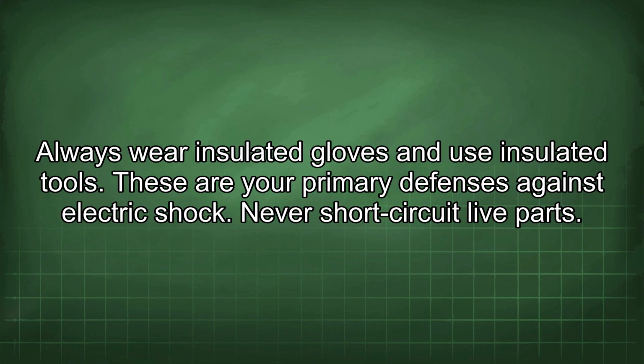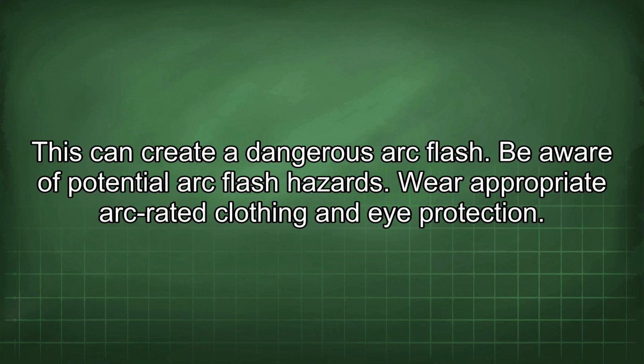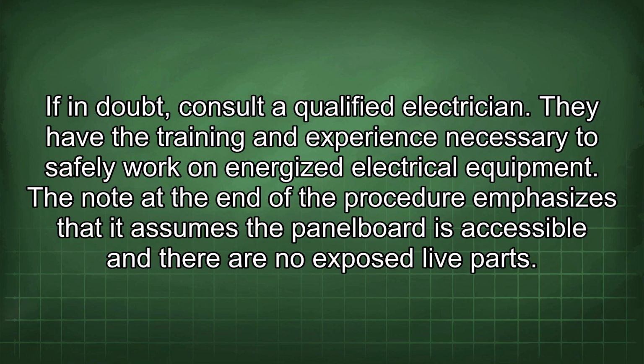Always wear insulated gloves and use insulated tools. These are your primary defenses against electric shock. Never short-circuit live parts. This can create a dangerous arc flash. Be aware of potential arc flash hazard. Wear appropriate arc-rated clothing and eye protection. If in doubt, consult a qualified electrician. They have the training and experience necessary to safely work on energized electrical equipment.